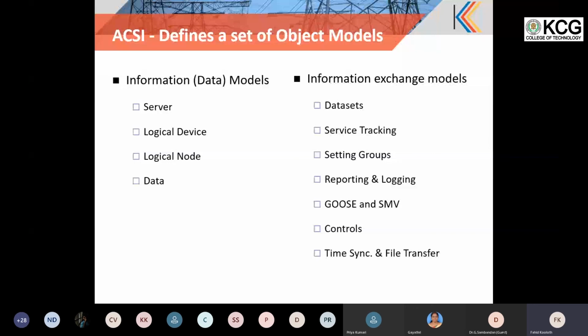Then control mode, like breaker operation, other things can be done using the control mode. Then time sync, that is SNTP, Simple Network Time Protocol, is used for the time sync in 61850. File transfer is essential for sending disturbance records and others as per the standard. So this is the overview of the abstract communication service model.